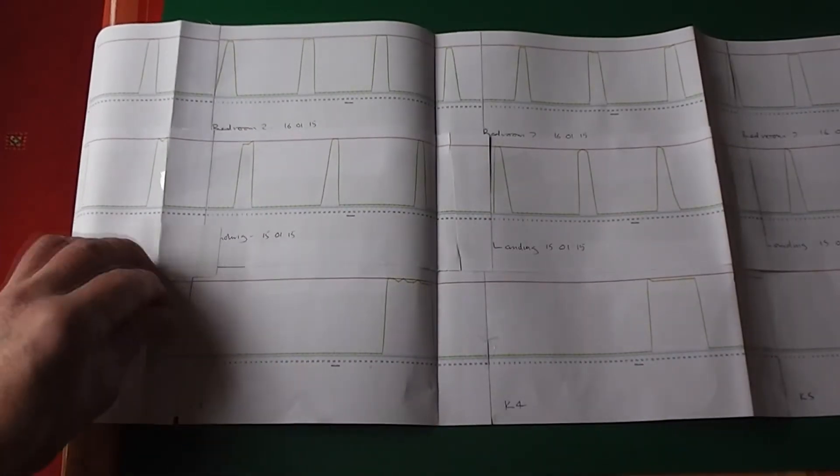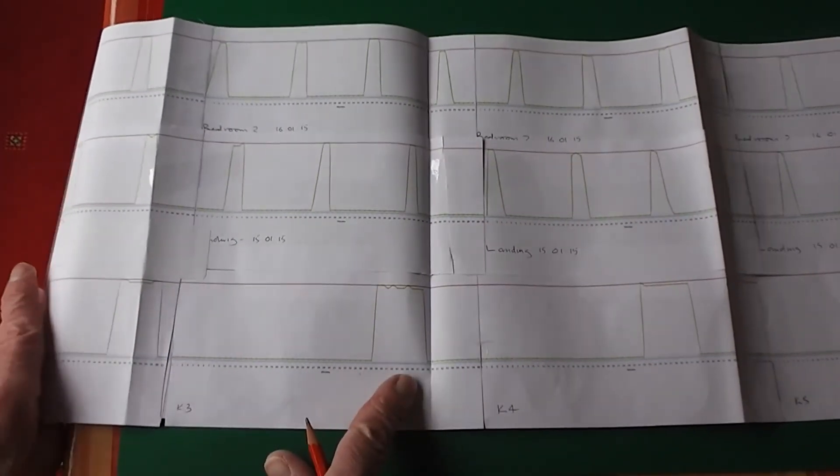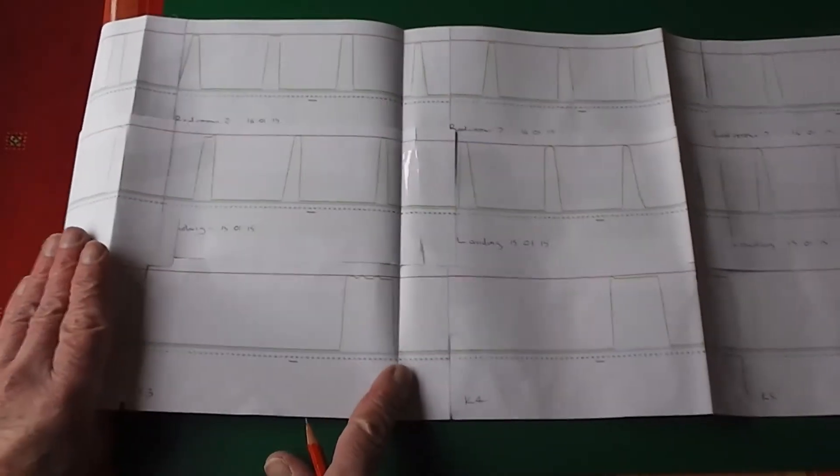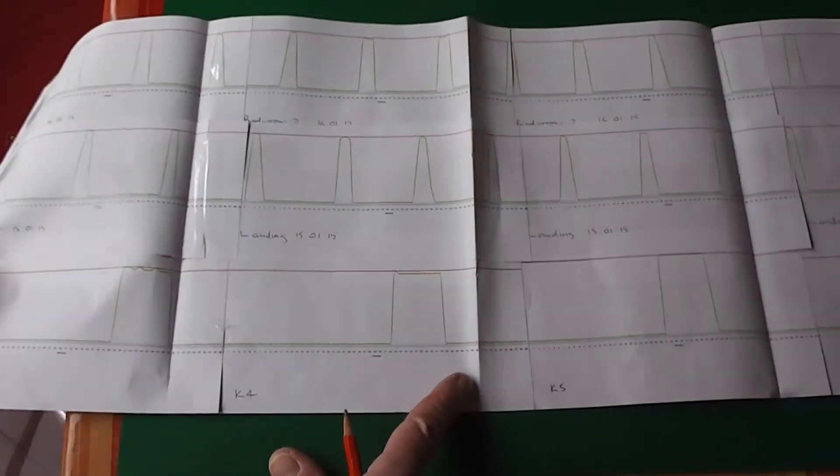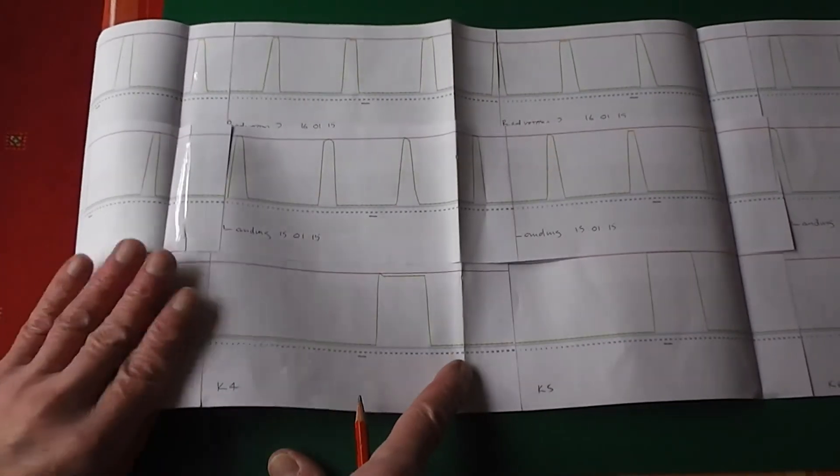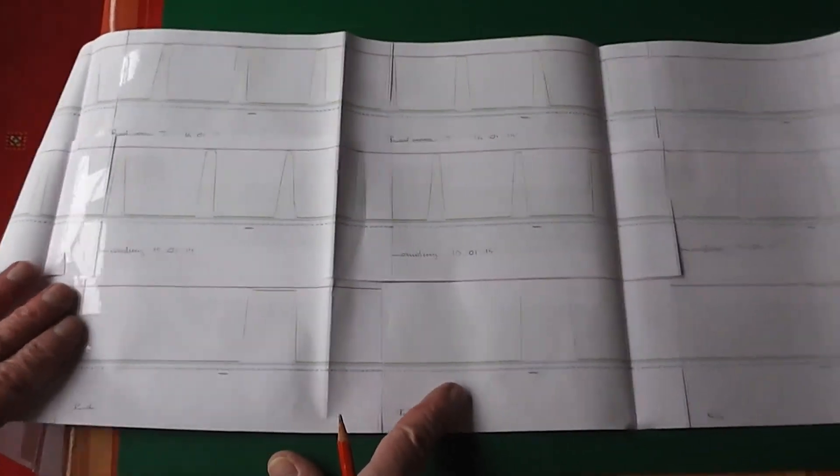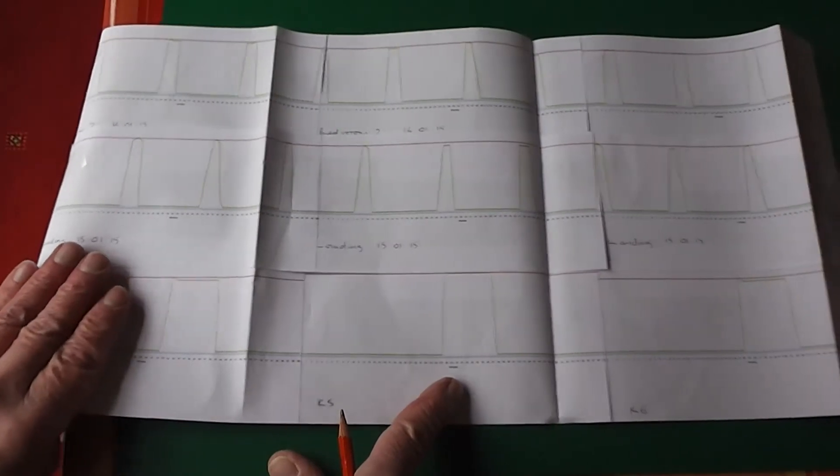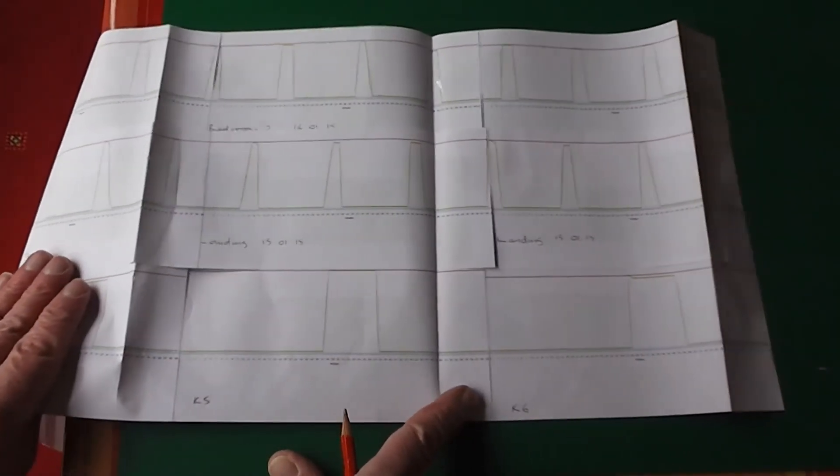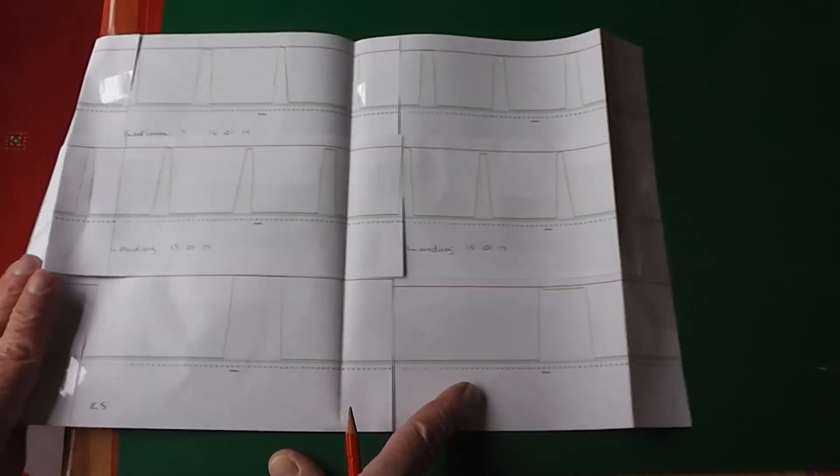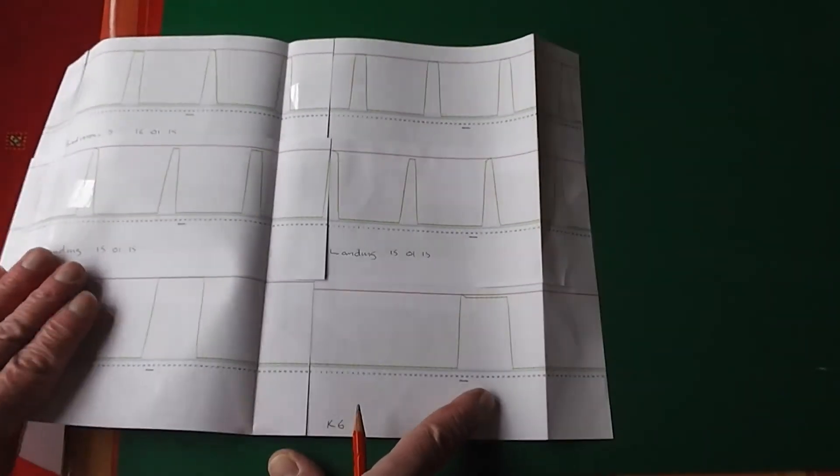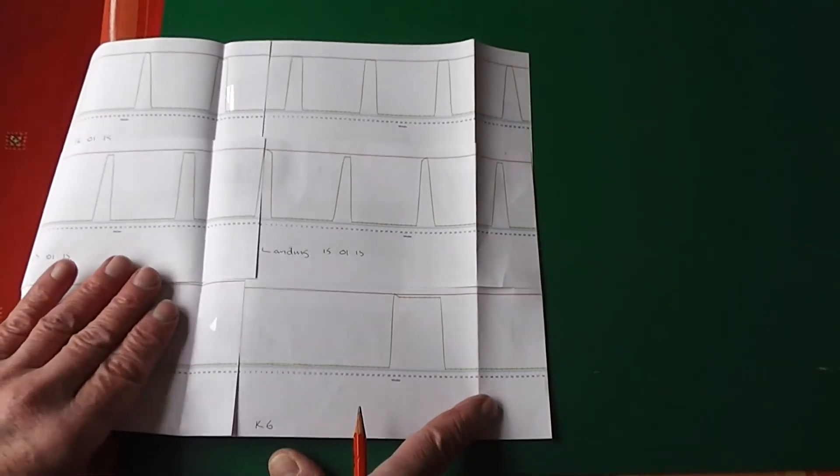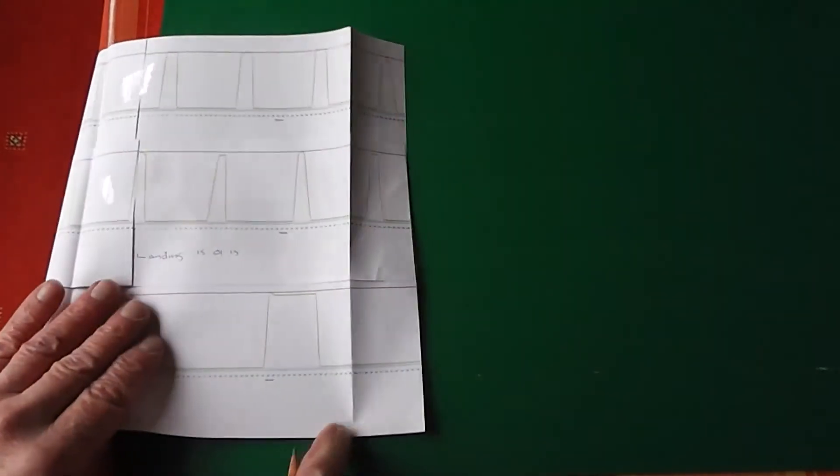And it's so important that these panel heaters are set correctly and that the thermostats are working properly. It's quite unlikely that you would notice until you saw the electricity bill. And using this energy monitor in this way does prove that all the thermostats are working correctly, turning on and off as they should throughout the 24 hour period and over the five days.